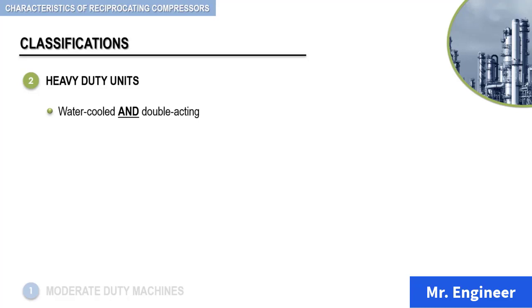The heavy-duty water-cooled reciprocating compressor has a relatively slow rotative speed between 180 to 900 RPM. These machines are designed for long service life at low maintenance costs. It is not unusual for this type of machine to be in operation even for 50 years after installation. Because they are conservatively designed with water-cooled cylinders, they are heavier, more expensive to manufacture, and more expensive to install than the other types of compressors.